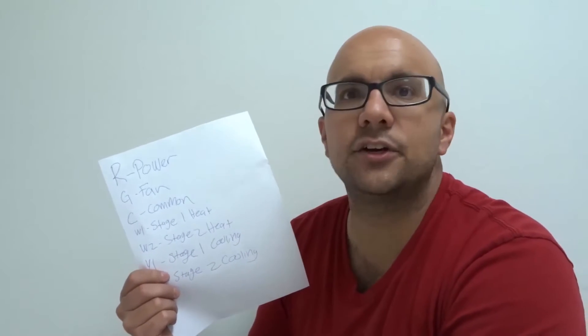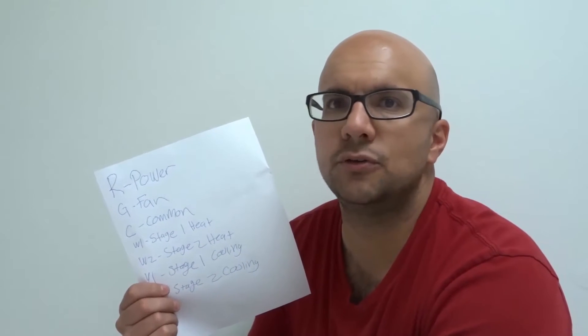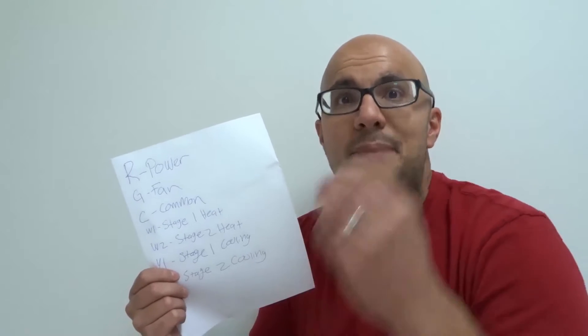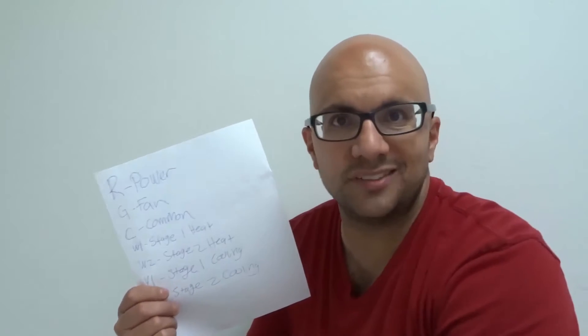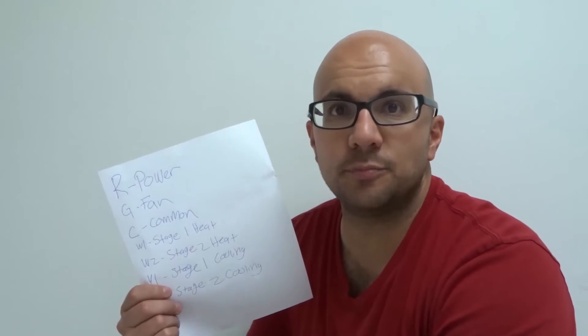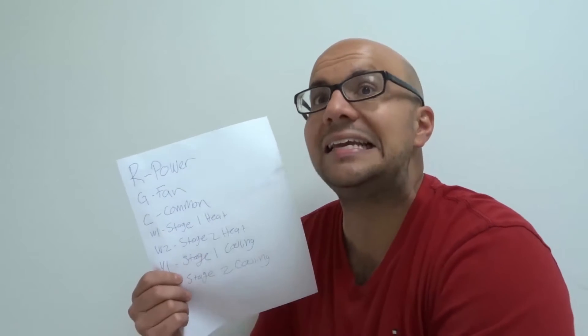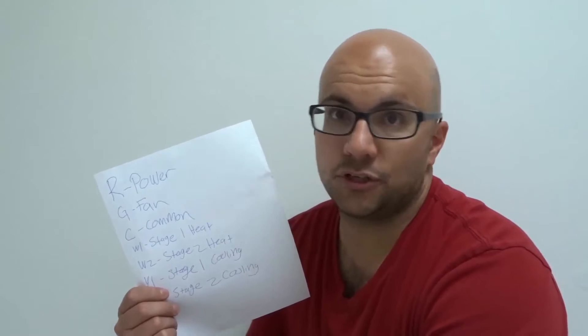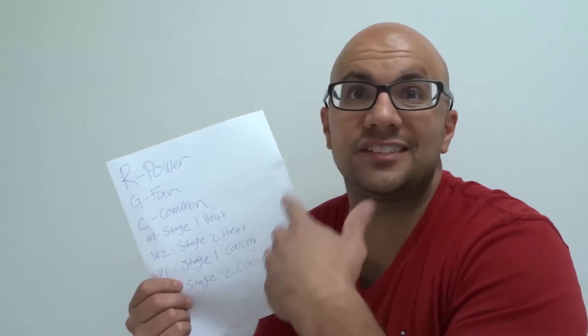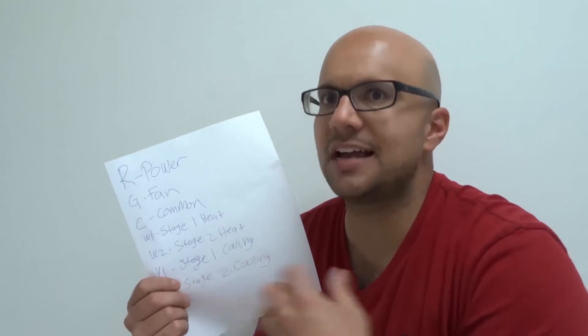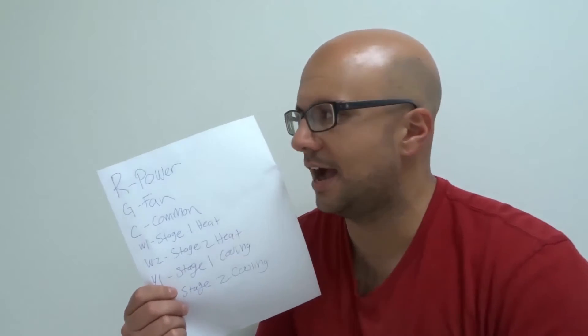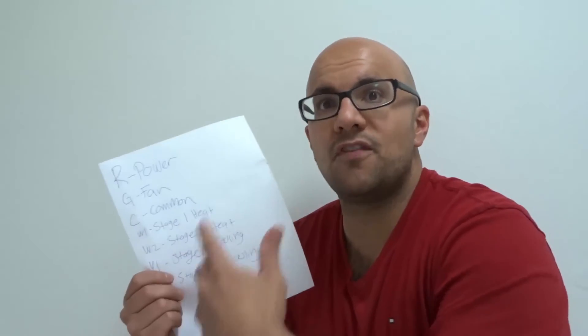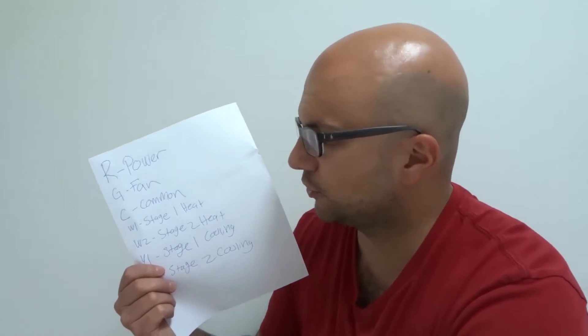C is your common wire, which is oftentimes used to provide power to the thermostat. If you're using a smart thermostat, you're going to most likely need a common wire, which they usually use as a blue wire or even sometimes a black wire. Not all the time, but most of the time, your common wire will provide power to your smart thermostat.